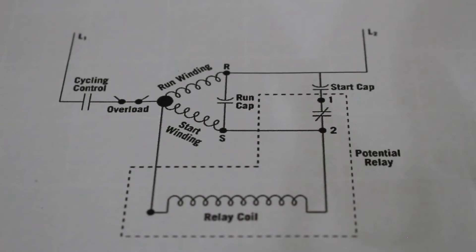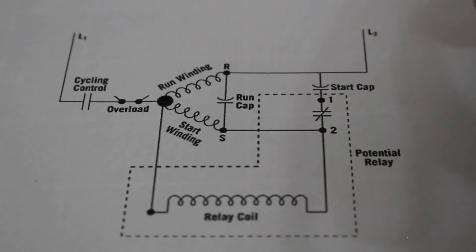The potential relay is not like other relays. Definitely not your basic control relay. It has a specific purpose, and the main goal is to help this system start by allowing the flow of electricity to your start cap. But once your compressor is up to speed, we want to remove the start cap from the circuit. So, let's go over.